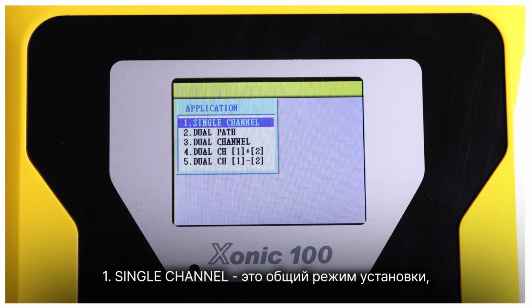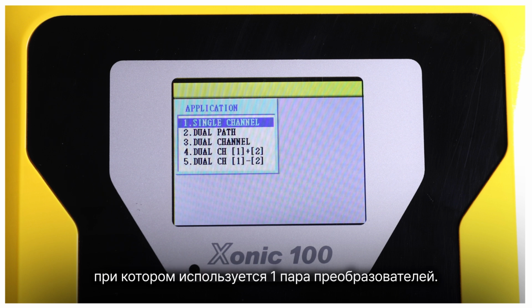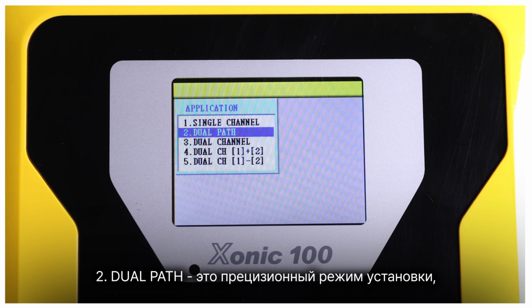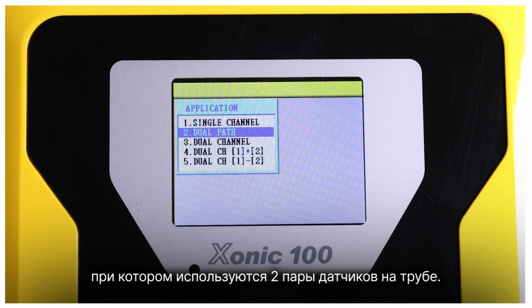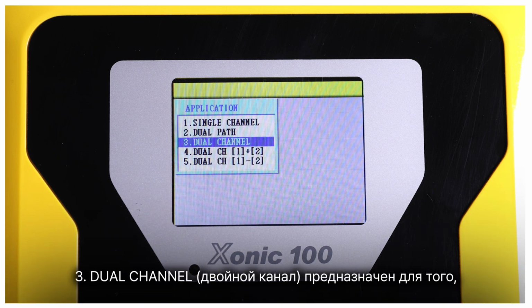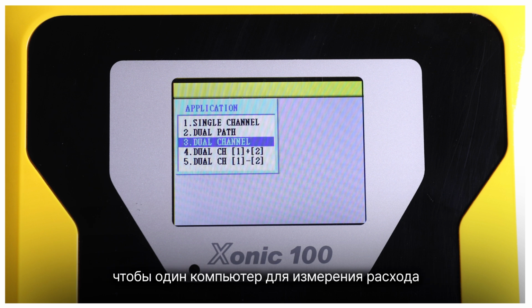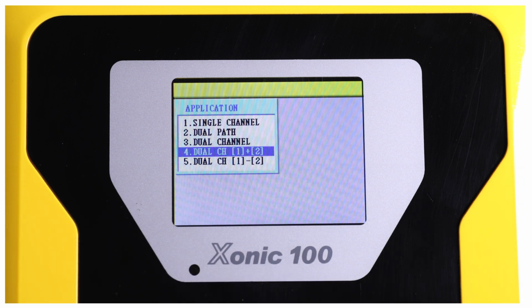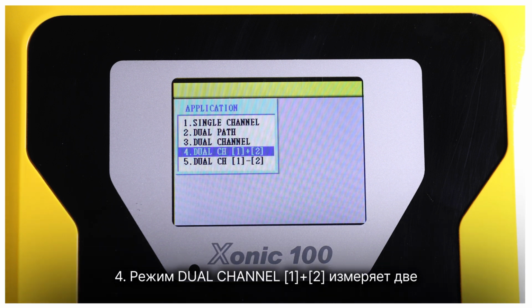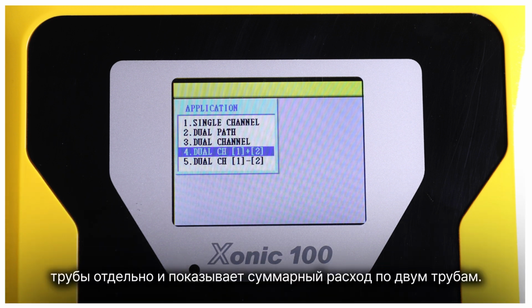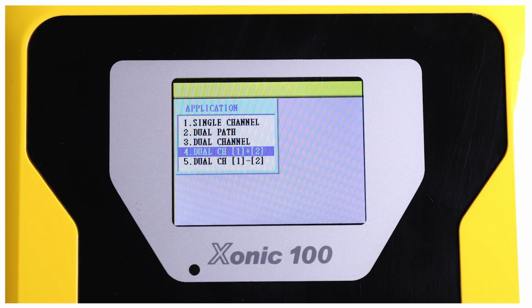1. Single channel is the general mode of installation that uses one pair of transducers. 2. Dual path is the precision mode of installation that uses two pairs of transducers on the pipe. 3. Dual channel is for one flow computer to measure two separate pipes simultaneously. 4. Dual channel 1+2 mode measures two pipes separately and shows the total of the two flow rates.